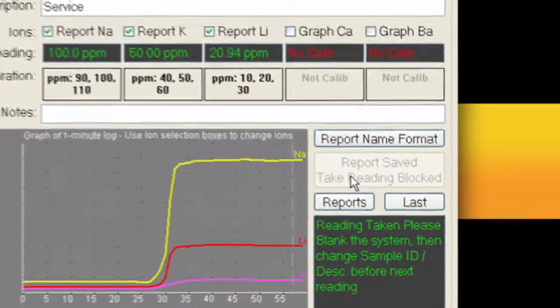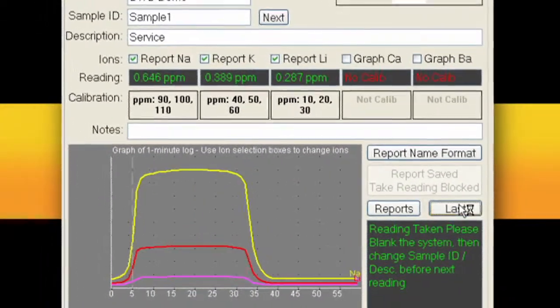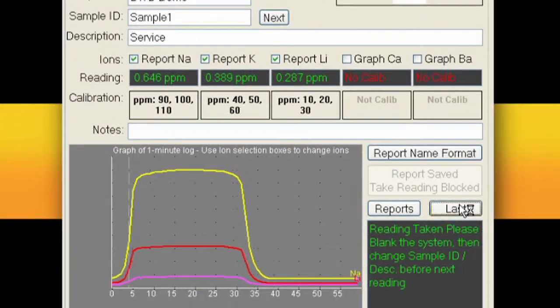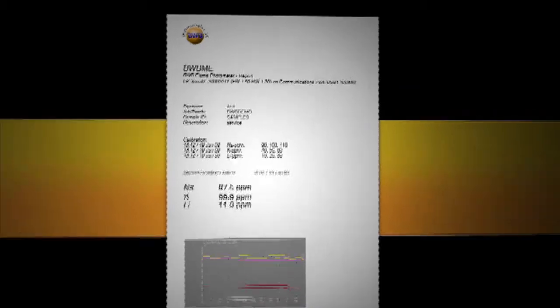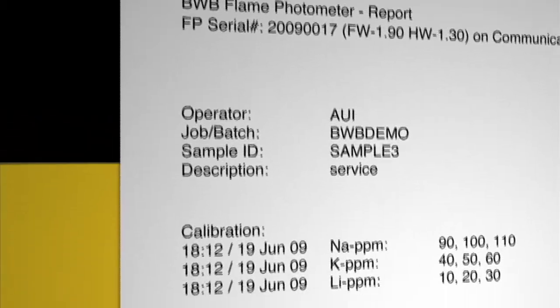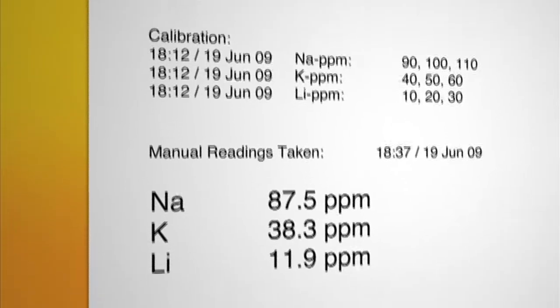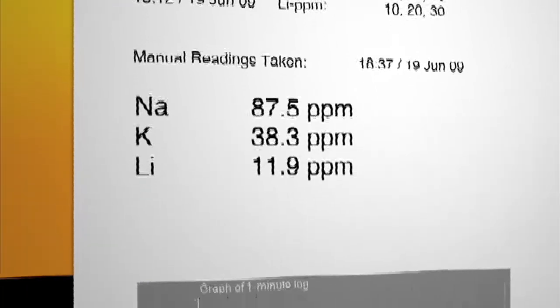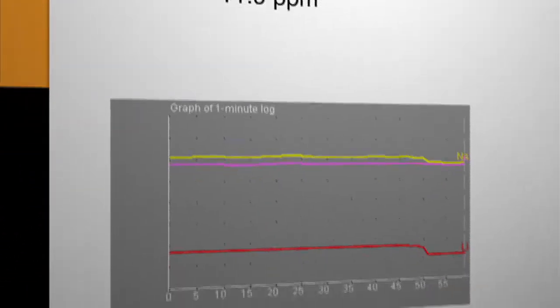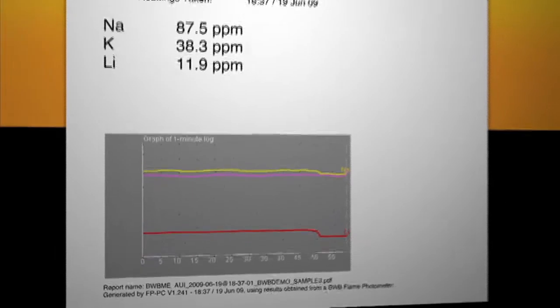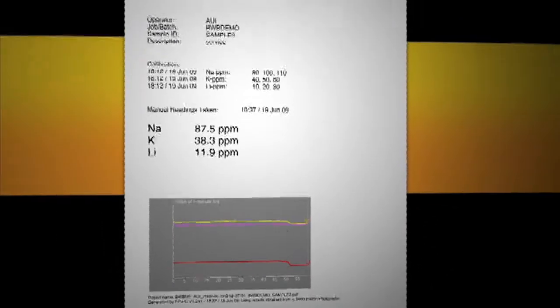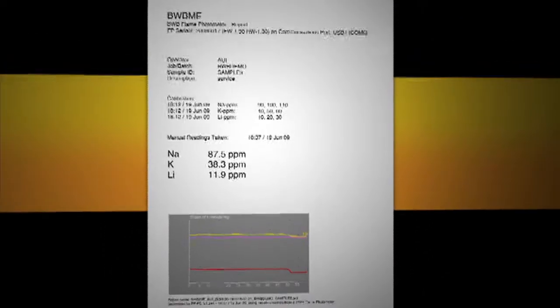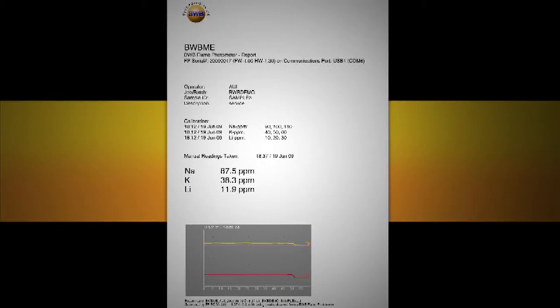Retrieve the report by ticking the last button. Your report will then be generated and will include the selected logo, operator details, date and time of the reading, calibration information and the one minute graph. This report can be stored electronically or printed and sent to colleagues. Truly a valuable tool in any modern laboratory.